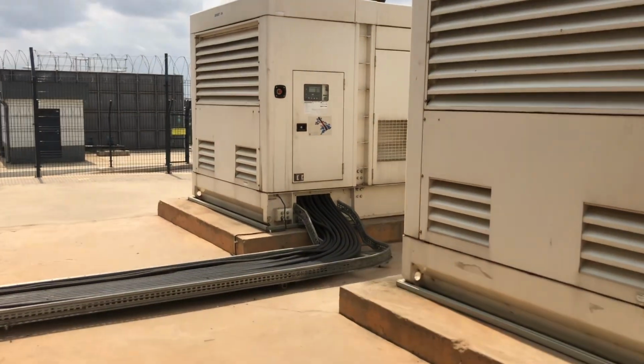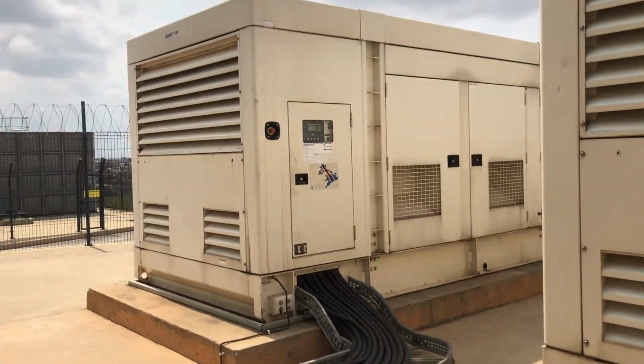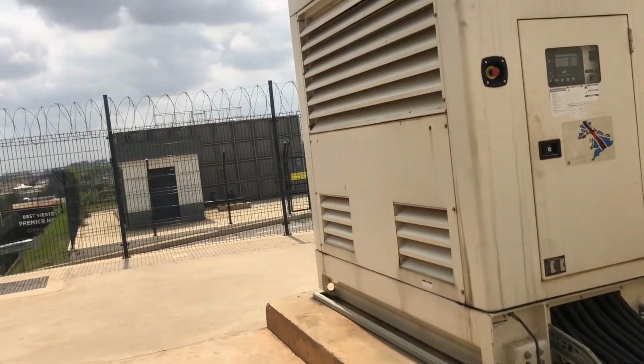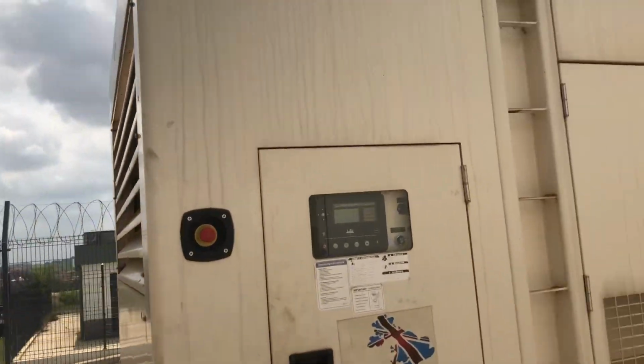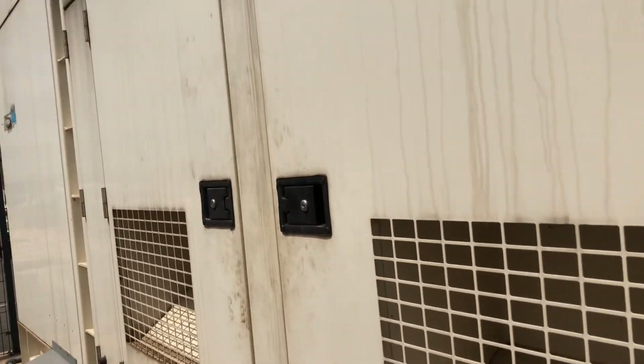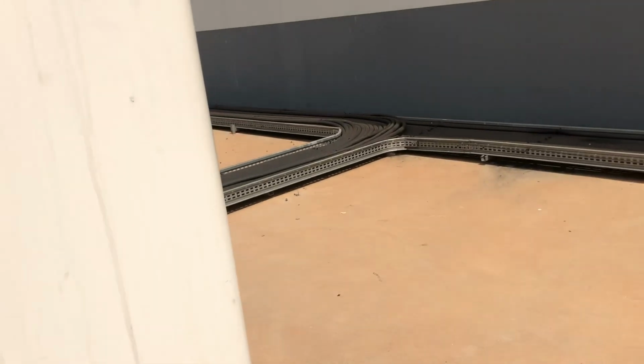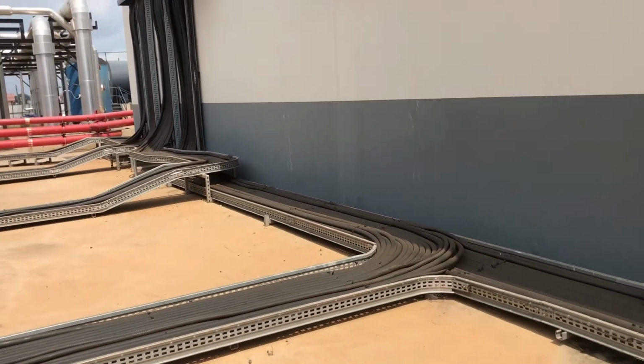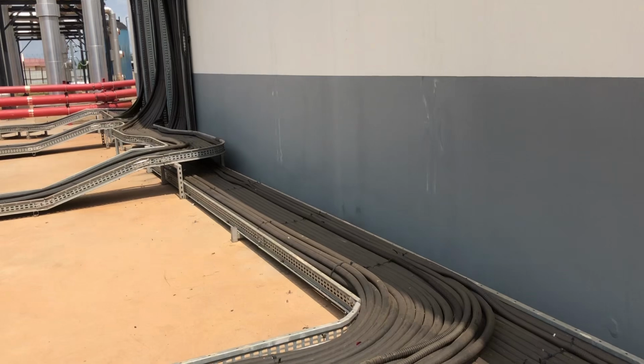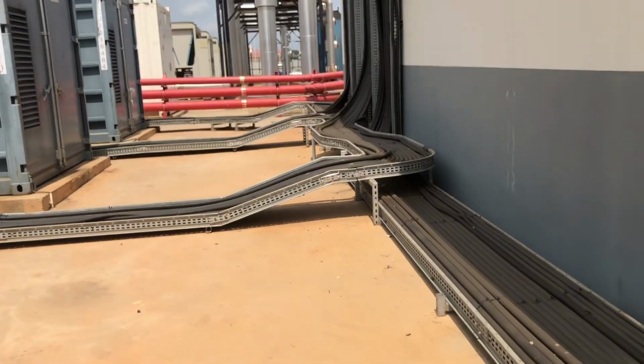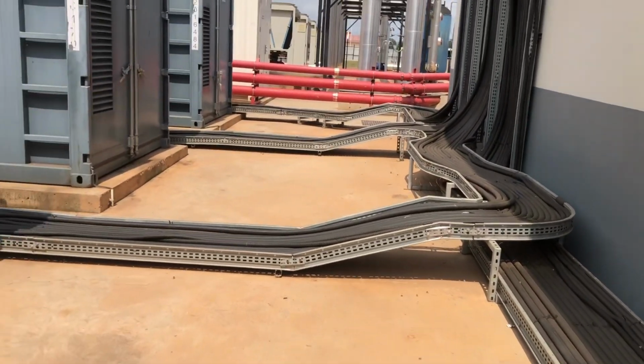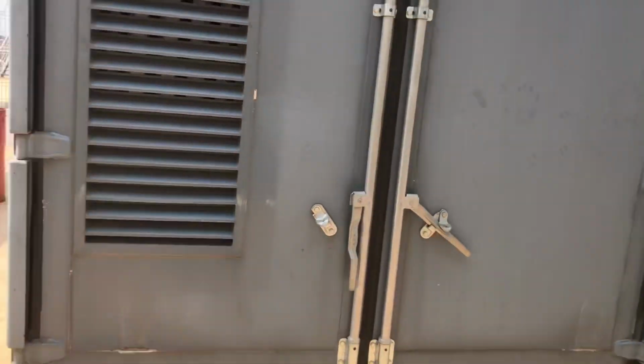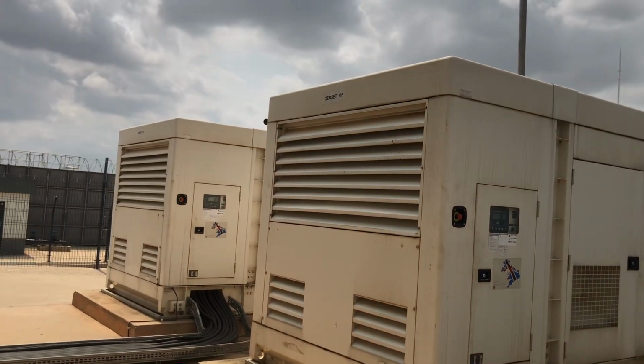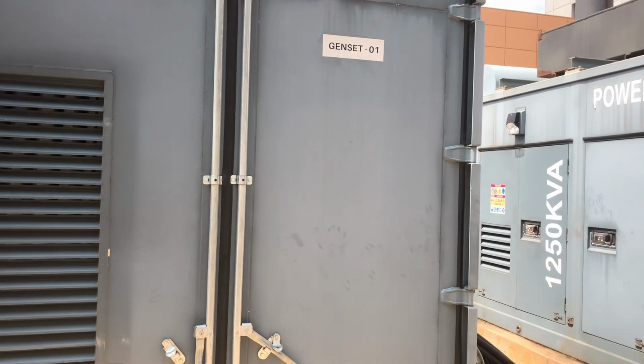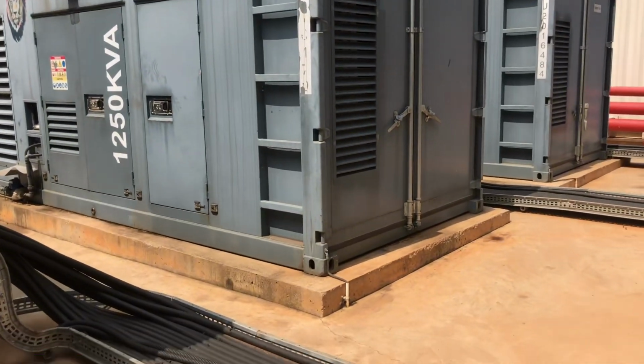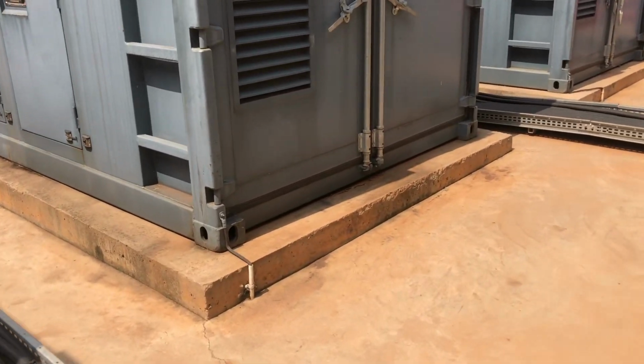To avoid that total blackout, we always check the genset panels at the totalizing unit to ensure they're set to auto mode. Once there's a power outage, the genset automatically, based on its schedule, takes over from the system, so we have power at both the terminal and the utility, maintaining power and avoiding total blackout at the airport.